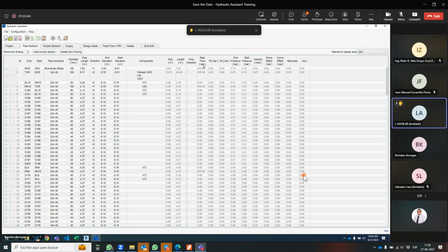Hi, my question is how to indicate the sprinkler pendant or upright? You don't have to specify that. You just have to specify the K factor. Same with the sidewall. There's no delineation. And same with the dry sprinkler. If you weren't aware, the K factor for the dry sprinkler heads, regardless of the barrel length, is actually calculated at the connection point. So it's just a K factor situation for you.